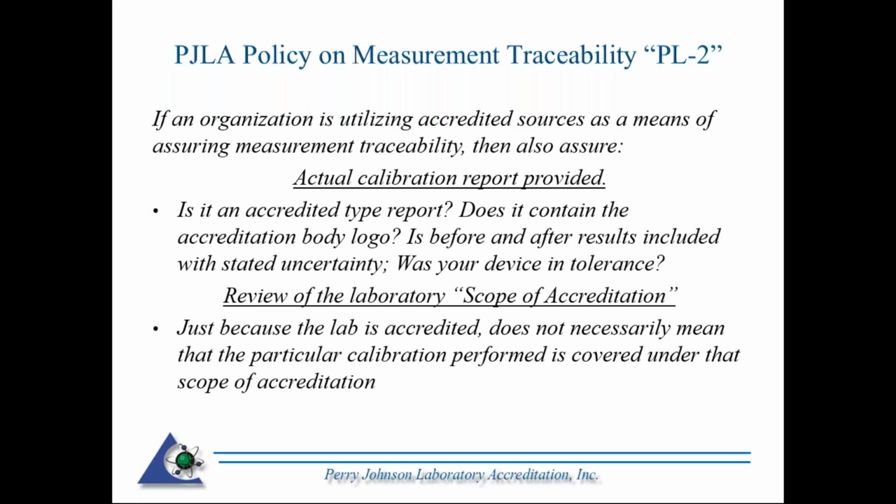Also, review the laboratory scope of accreditation. Just because an organization is accredited, you want to assure that they are accredited to perform the calibration that you need. And actually, this should be part of your evaluation under externally provided products and services, i.e. purchasing, where you are required to evaluate your suppliers and monitor them, and have some sort of criteria in place for approving suppliers. So ideally, 17025 would be a good qualifier as far as approving a supplier for traceability reasons.